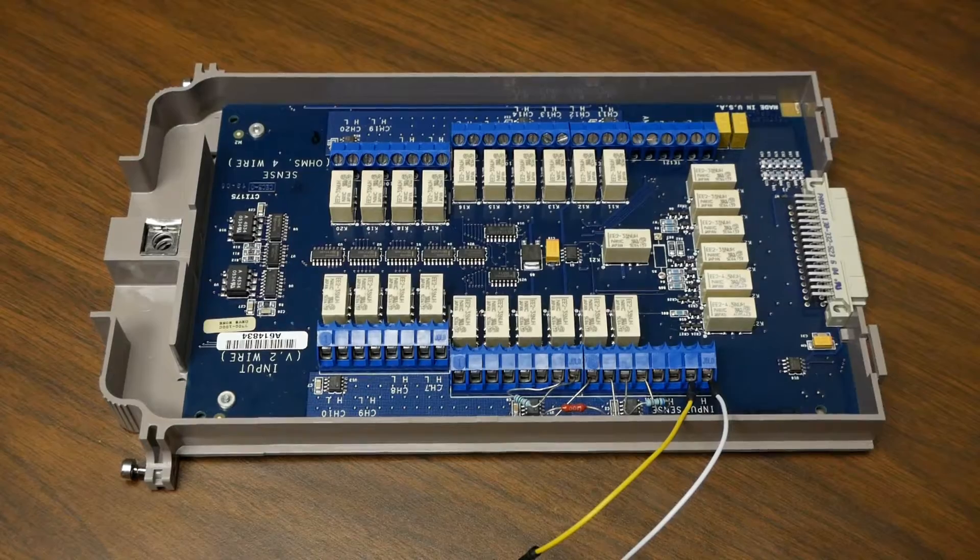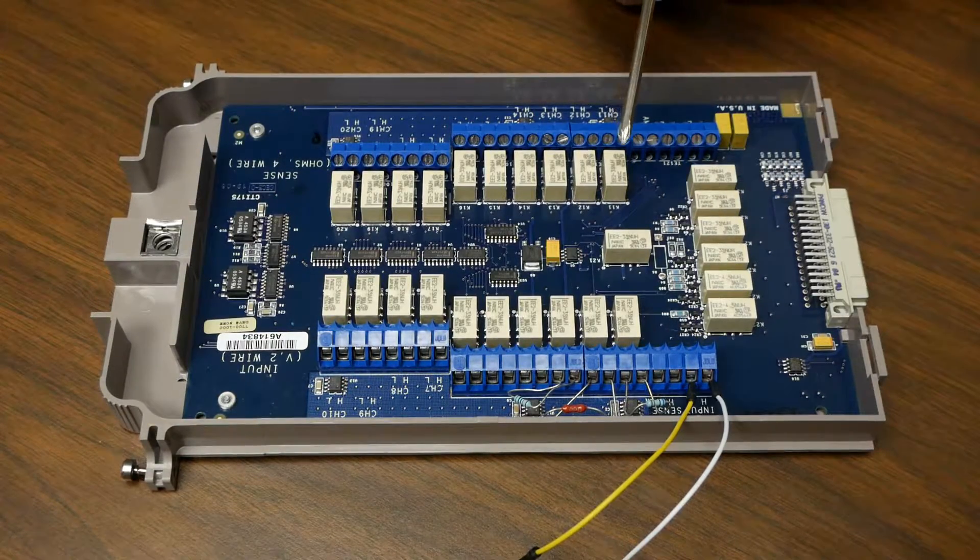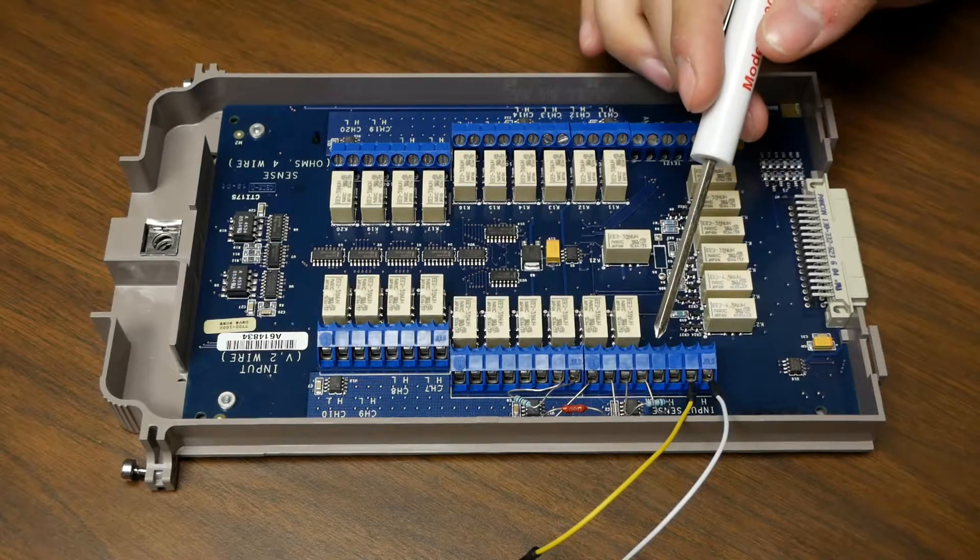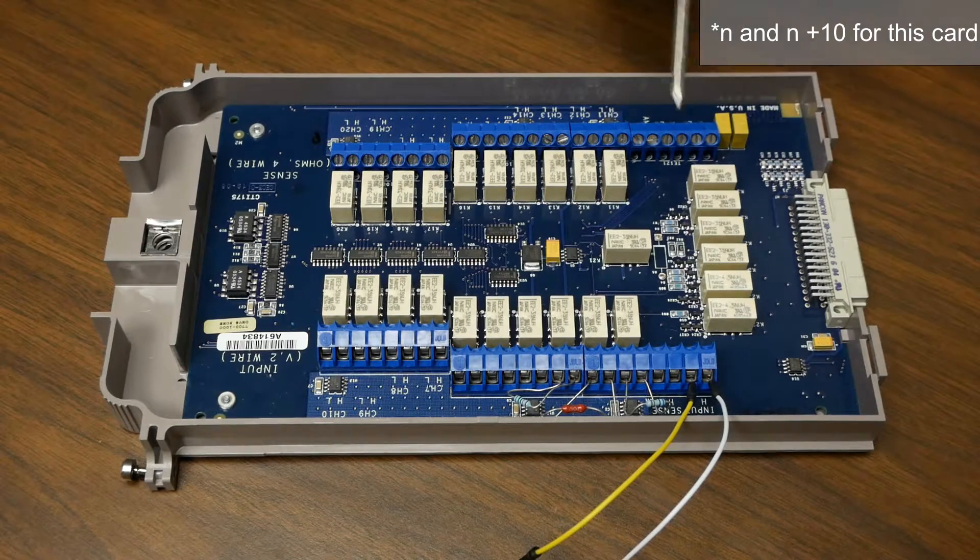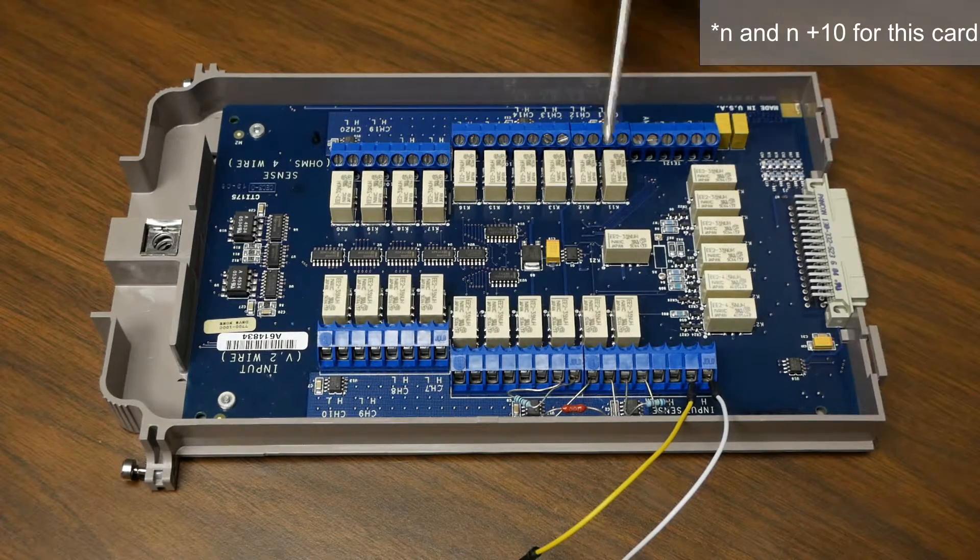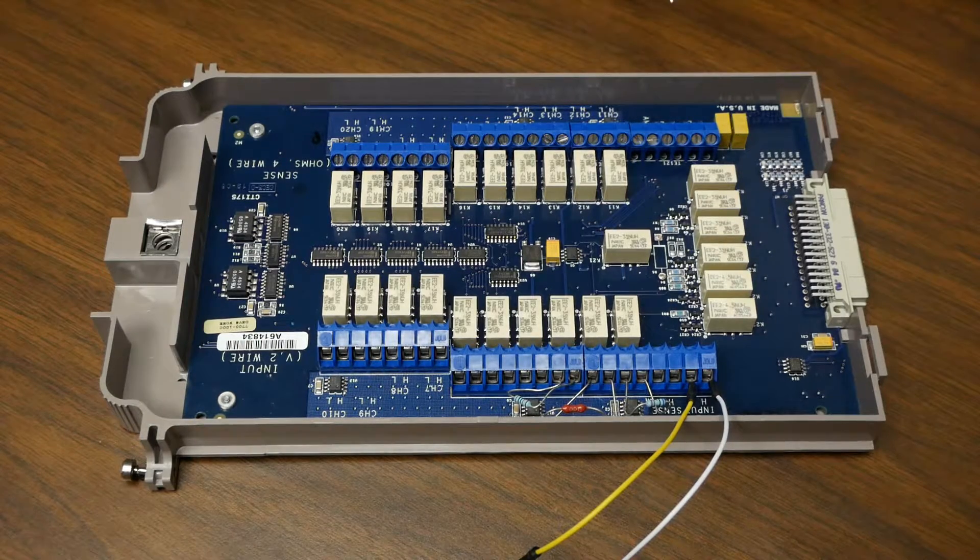If you were to run a four-wire test, not only would we have our sense connections, but also you would need to connect your resistors or your DUTs on the N and N plus 10 channels to get all four-wire connections. For example, channel one would have the high and low and channel 11 would have the sense high and low of your DUT.